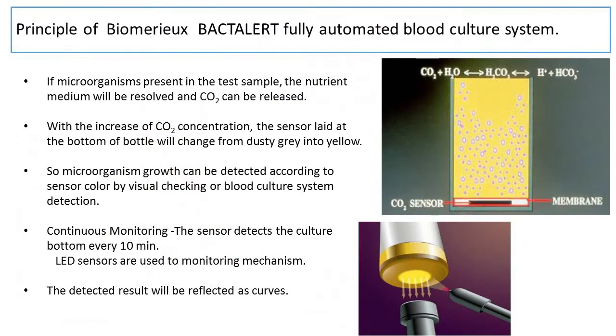If microorganisms are present in the test sample, the nutrient medium will be consumed and CO2 is released. With the increase of CO2 concentration, the sensor located at the bottom of the bottle will change color from dusty gray to yellow. Microorganism growth can therefore be detected according to sensor color by visual checking or by the blood culture system.